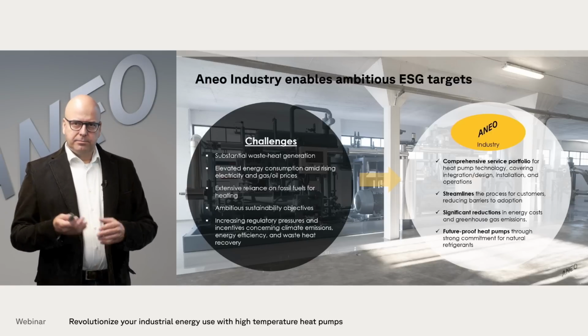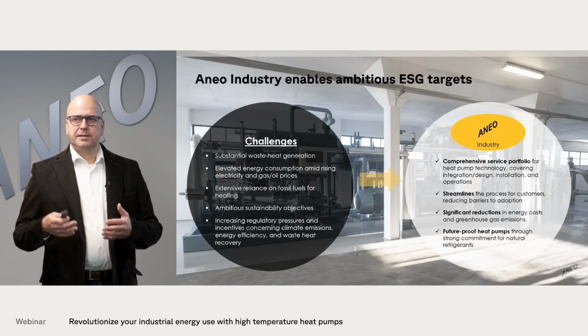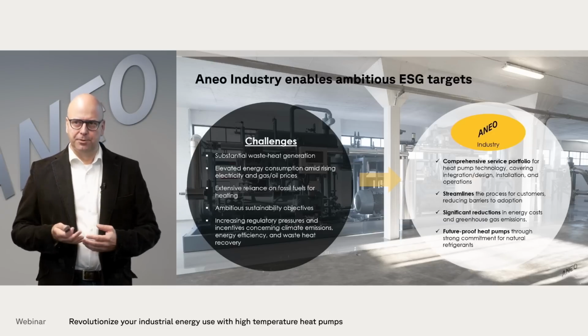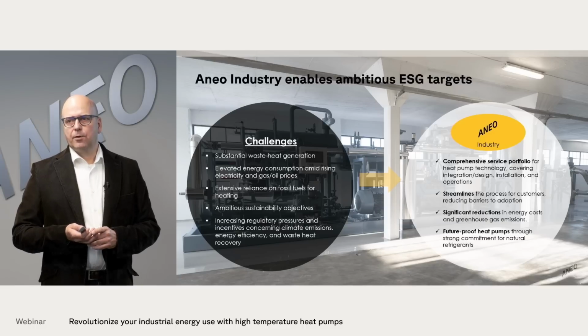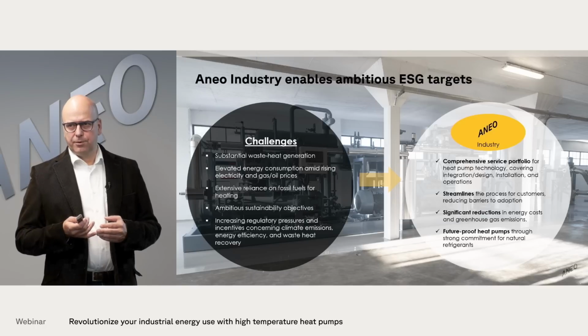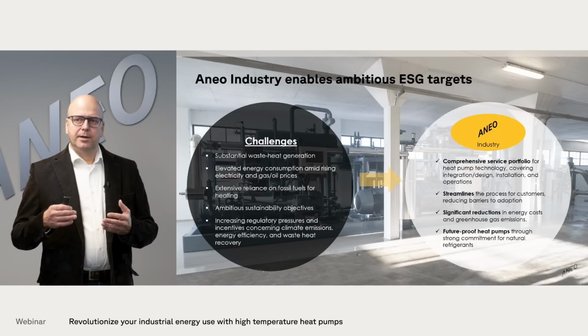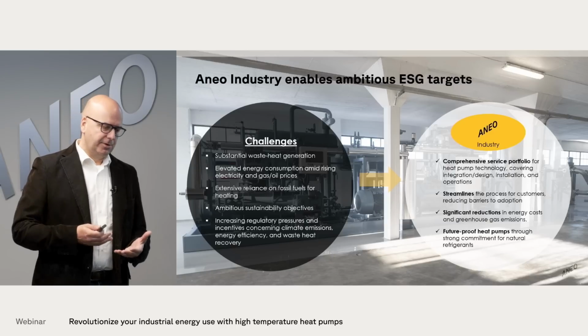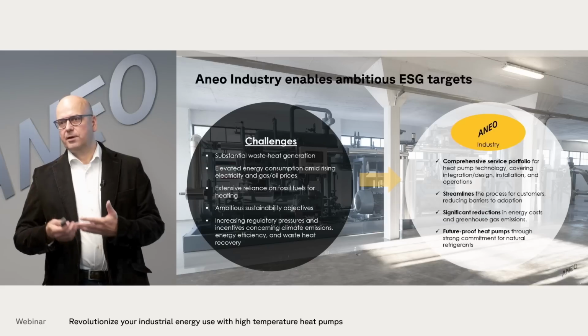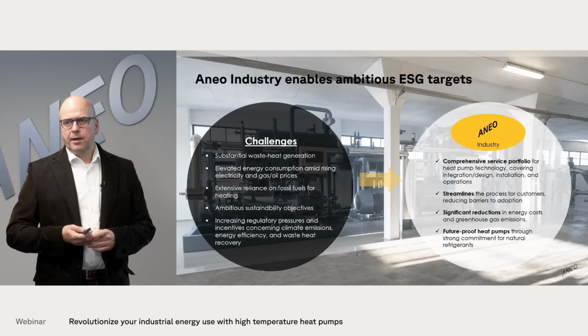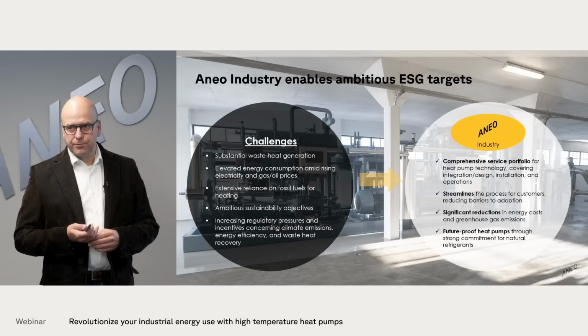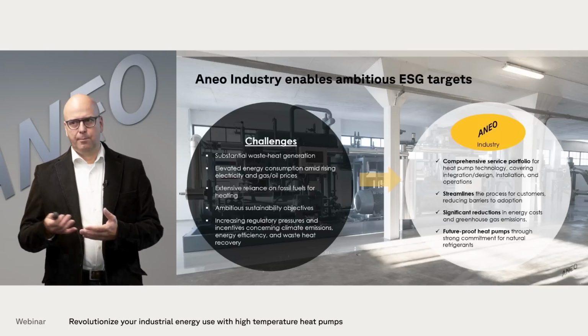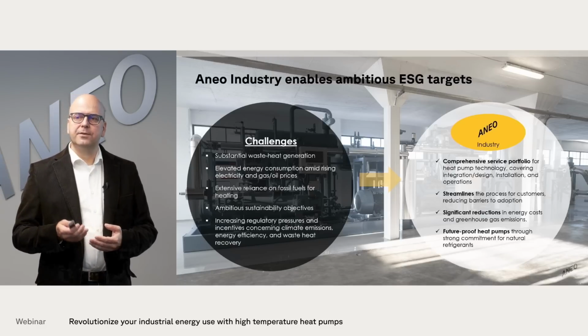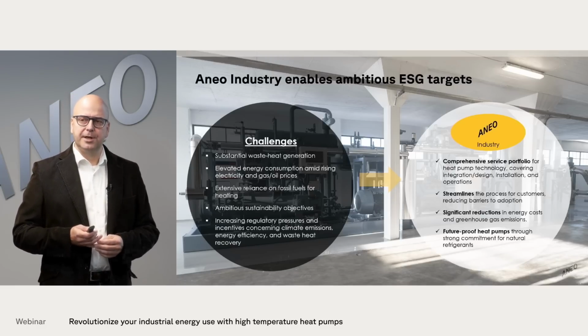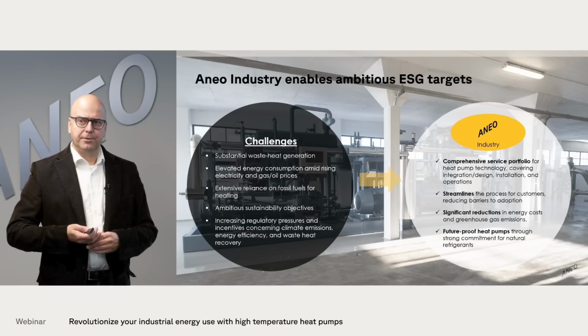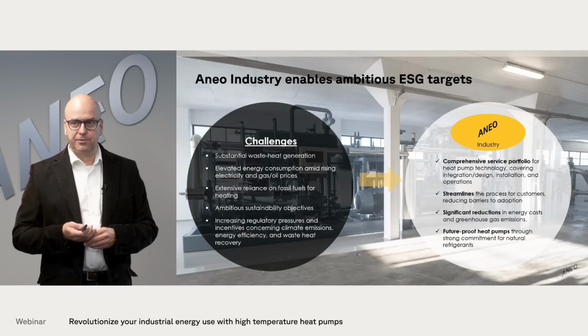In Aneo now, we are taking this customer and we are basically buying a heat pump, installing it on the customer site and operating it for the customer. So this is a very comprehensive service portfolio for heat pump technology, which enables the customer to get significant reductions of CO2 emissions without having capex costs upfront. I would also outline that we are using a future-proof heat pump concept based on natural refrigerants, basically ammonia and water as refrigerant. And Cordin also outlined in this presentation that ammonia and water is one of the natural refrigerants which had the highest acceptance by the market.